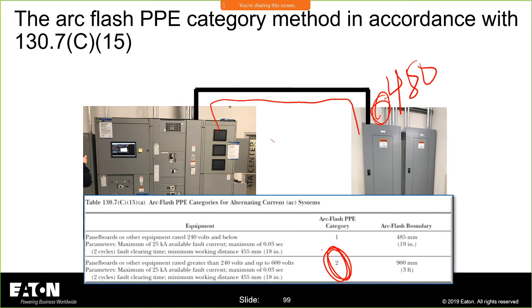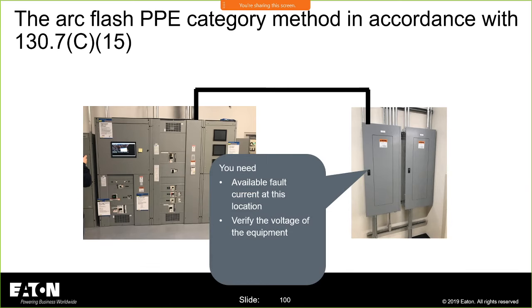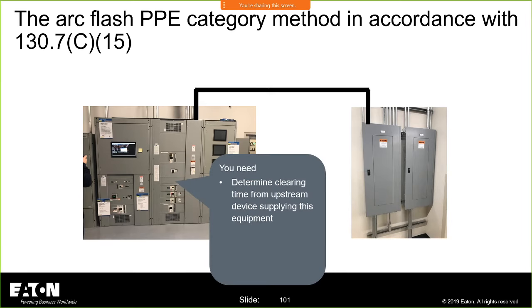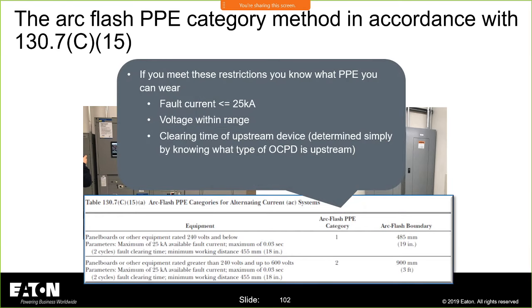If there's a transformer in this switchboard that's feeding this, or if there's a transformer upstream, I can use the Bussmann FC² app to estimate my fault current at this panel, and then I would know if it's less than or equal to 25,000 amps, I'm downstream of a molded case circuit breaker, I am in PPE category 2. That's how they do the table method. I estimate the available fault current at that location. I determine that clearing time from the upstream device.